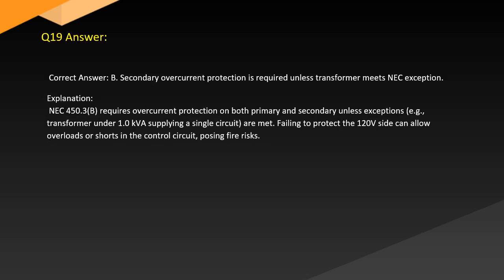Answer. Correct answer: B. Secondary overcurrent protection is required unless the transformer meets an NEC exception. Explanation. NEC 450.3(B) requires overcurrent protection on both primary and secondary unless exceptions, e.g. a transformer under 1.0 kVA supplying a single circuit, are met. Failing to protect the 120 volt side can allow overloads or shorts in the control circuit, posing fire risks.